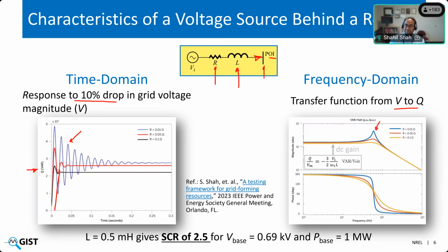Below the fundamental frequency, the gain is pretty much flat or constant, and the phase is 180 degrees. This intuitively makes sense, because the voltage source behind reactor will act as a negative DC gain in the subsynchronous frequency range in the transfer function from V to Q. The negative gain shows that if the voltage goes down, the reactive power output of the voltage source behind reactor will go up.